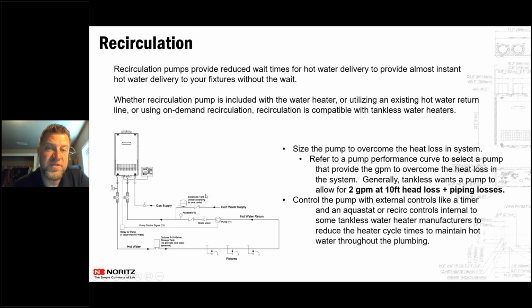And then that pump that you're choosing to put in there, just make sure that pump is at least 2 gallons per minute or more. Even though that unit only has a ½ gallon per minute to fire, you want something large enough that if you've got 33 feet of head pressure going off there, that 2 gallons per minute might drop down to 0.4, 0.3 gallons per minute, and it won't fire that unit. So you want something that's 2 gallons per minute or more. That's kind of the rule of thumb to make sure that unit's going to fire correctly.